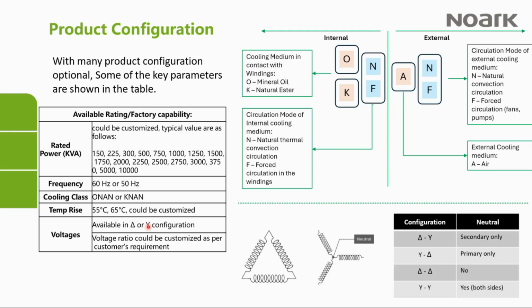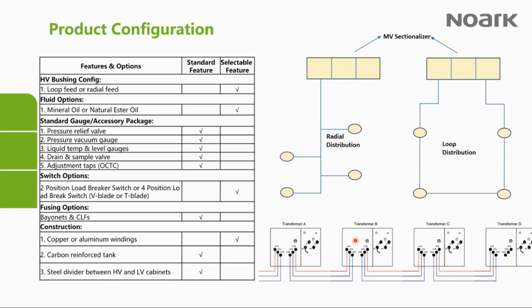The other thing that you would see in the transformer is the configuration, which is also called the vector group. So we can do whether it's a delta or a wye combination. We can do any of them, basically. A delta just means that all the windings are connected together this way. And for a Y, it means that one end of the coils are all connected to one point, which will become the neutral. So we can do any of these configurations depending on what the customer wants for their application.